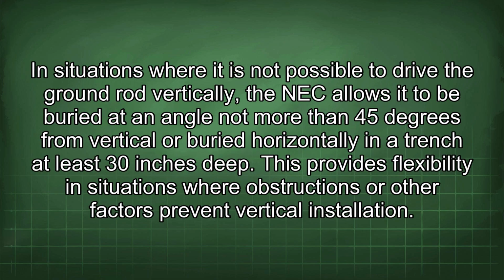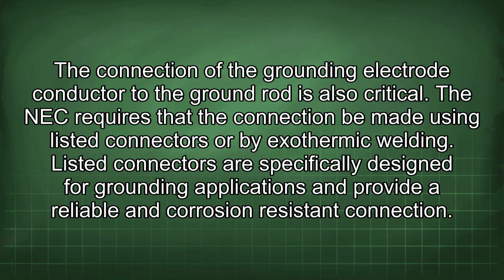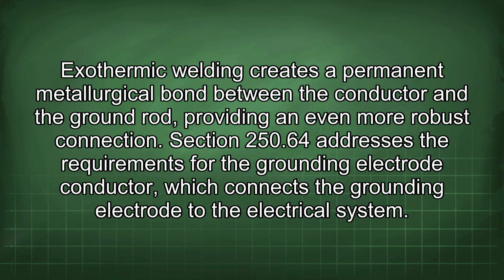In situations where it is not possible to drive the ground rod vertically, the NEC allows it to be buried at an angle not more than 45 degrees from vertical or buried horizontally in a trench at least 30 inches deep. This provides flexibility in situations where obstructions or other factors prevent vertical installation. The connection of the grounding electrode conductor to the ground rod is also critical. The NEC requires that the connection be made using listed connectors or by exothermic welding. Listed connectors are specifically designed for grounding applications and provide a reliable and corrosion-resistant connection. Exothermic welding creates a permanent metallurgical bond between the conductor and the ground rod, providing an even more robust connection.